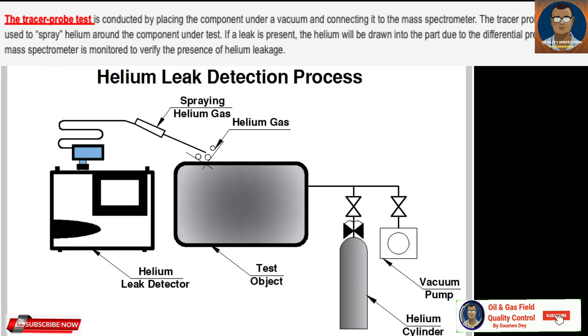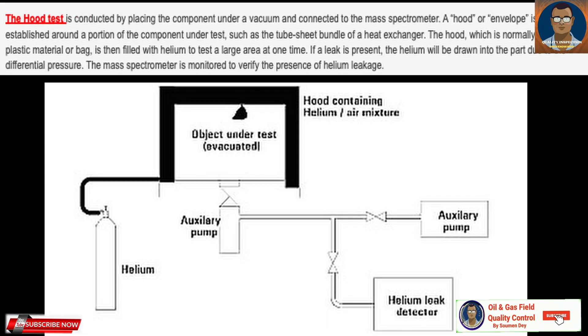The tracer probe test is conducted by placing the component under a vacuum and connecting it to the mass spectrometer. The tracer probe is then used to spray helium around the component under test. If a leakage is present, the helium will be drawn into the part due to the differential pressure, and the mass spectrometer is monitored to verify the presence of helium leakage.